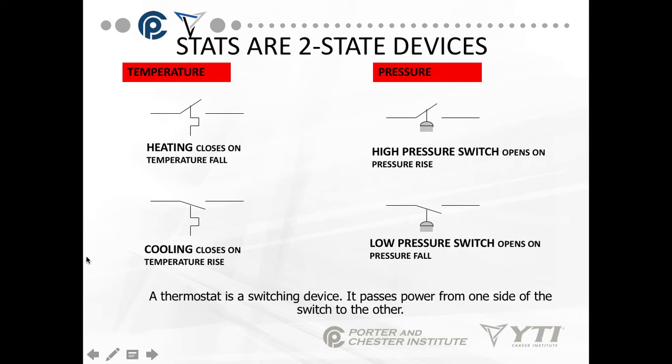The thermostat is a switching device — all it does is pass power from one side of the switch to another. It doesn't use power. So if you take a voltage reading across a thermostat, you should never have a voltage drop. If it's closed, it acts as a closed switch and should have zero volts. If it's open, it acts as an open switch and should have 120 volts.